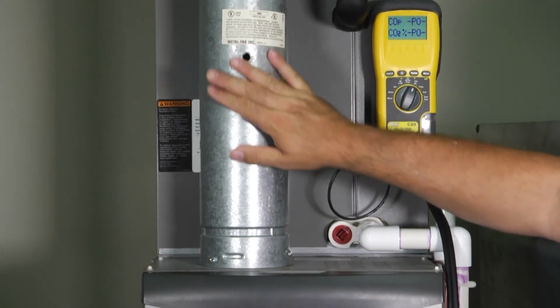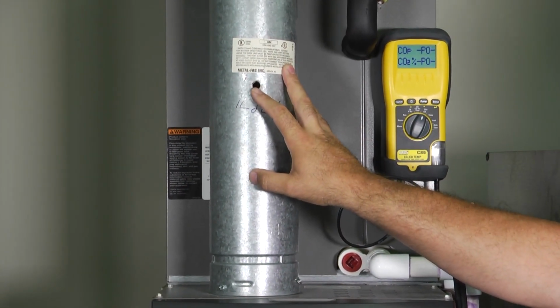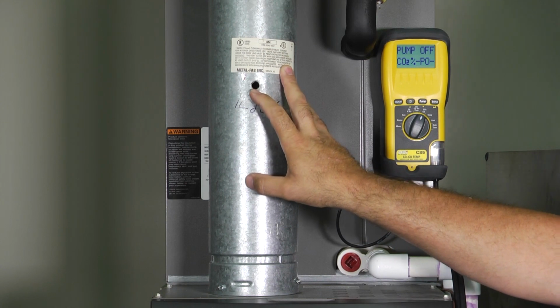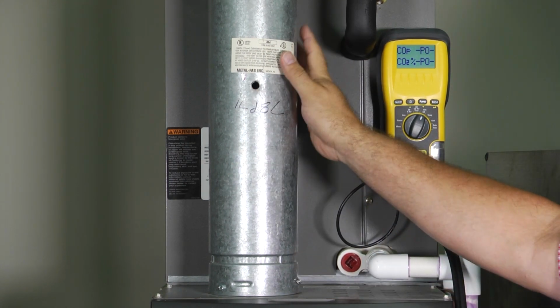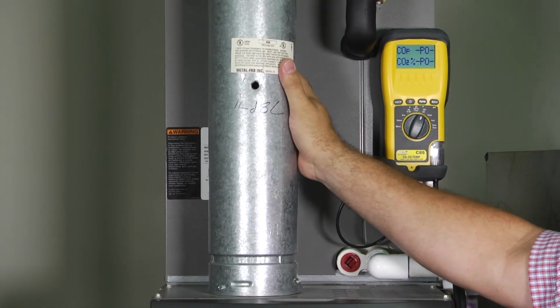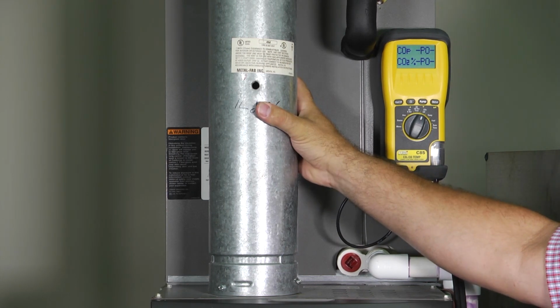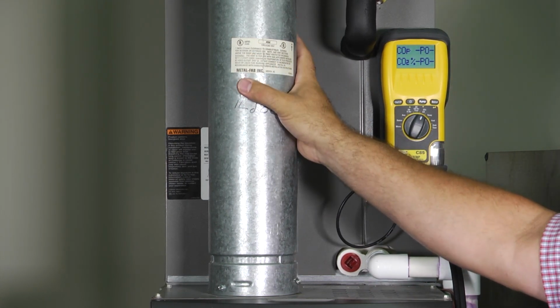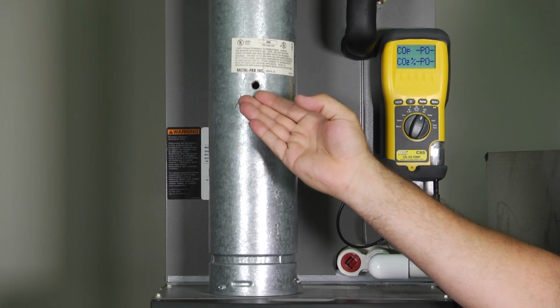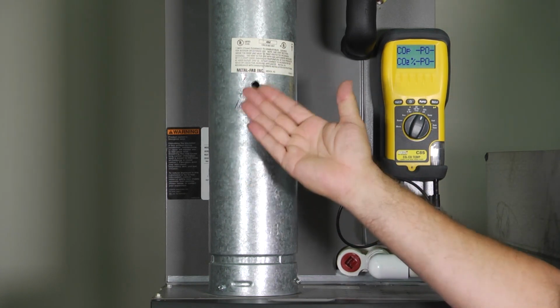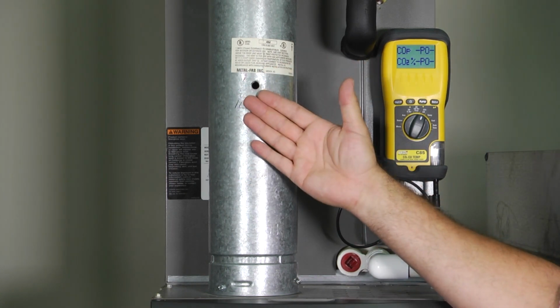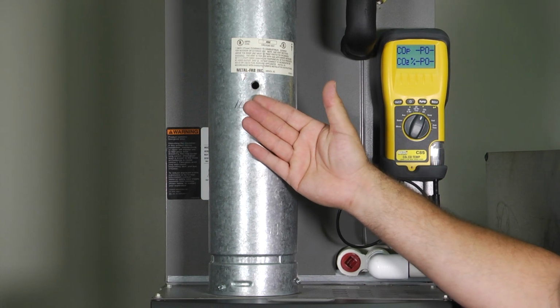And really when I talk about this, we say, well, Mark, that's great, but you've drilled a hole in it, you've now damaged it. Flue products can pour out of that. The thing to remember is that every B-vent or any chimney alone works on a negative draft principle. So unless there's a problem with my venting, no flue gases could ever spill out of there, because I'm always going to have air drawing in.